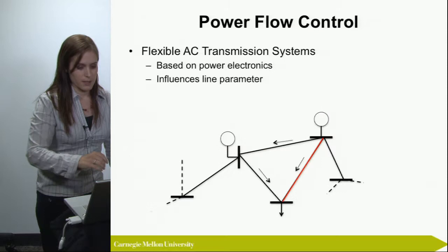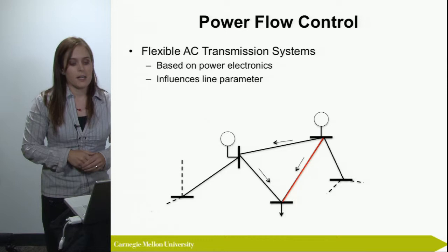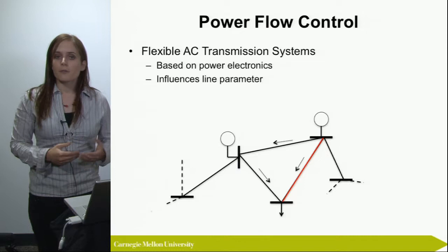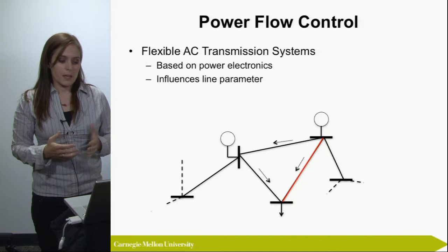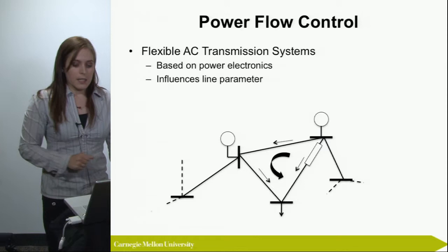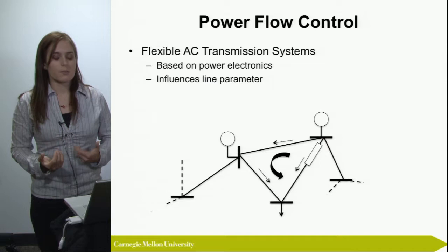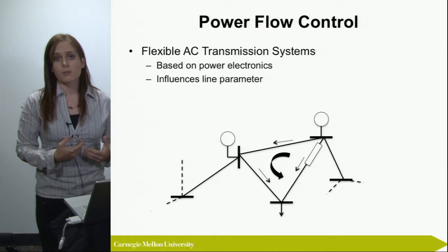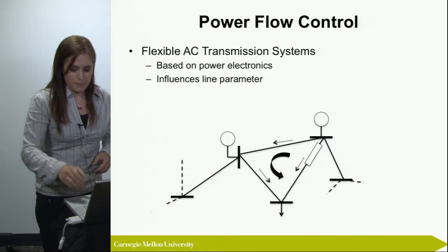Let's first talk about flexible AC transmission systems, or FACTS devices. These devices are based on power electronics and work by influencing the line parameters — specifically the reactance of a line — which determines how much power flows over it. If we place such a device in a congested line, it allows us to push some power over the parallel system. That means we can still use our cheap generator or increased wind generation at that location to supply the load.